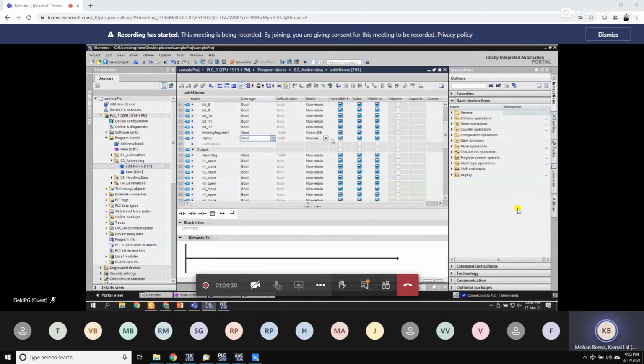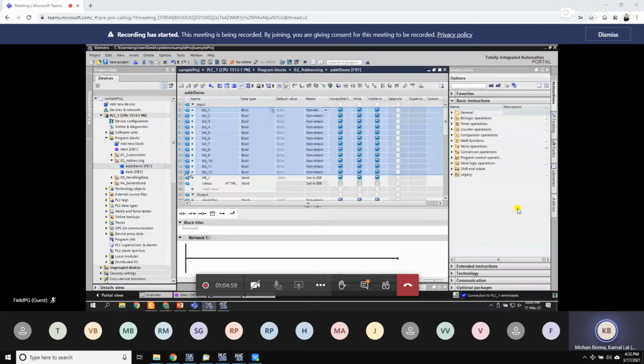But once you keep this option, you have the possibility to just type AT there. What the AT will do is overlay this status on top of that holding register 1. So let me make it simple. I'll call it HR1. I'm sick of seeing that. So this status tag is right now overlaid on top of that. To keep things simple, let me delete all the old ones.